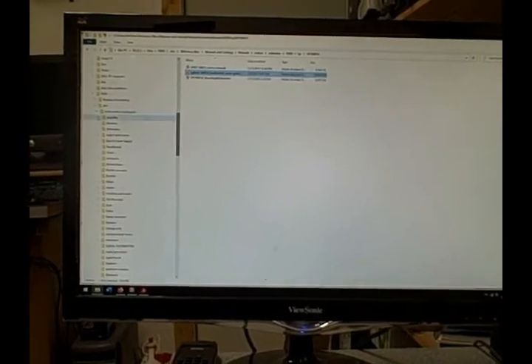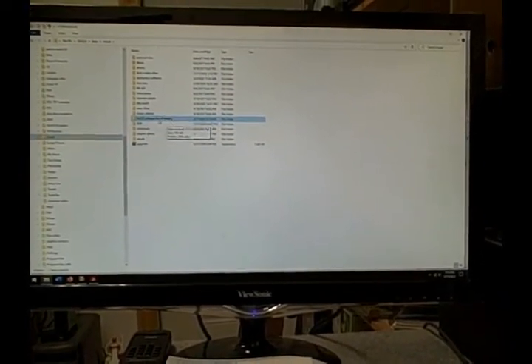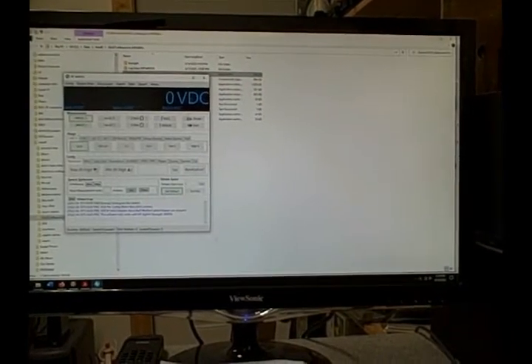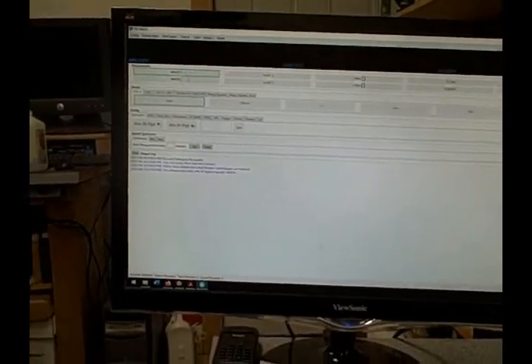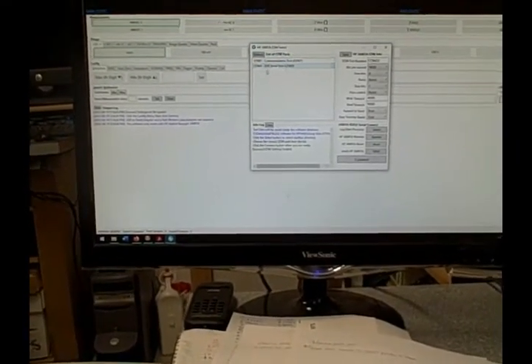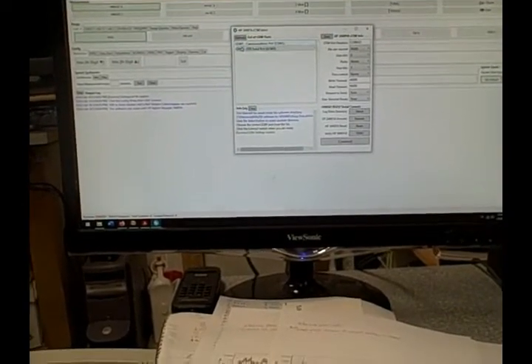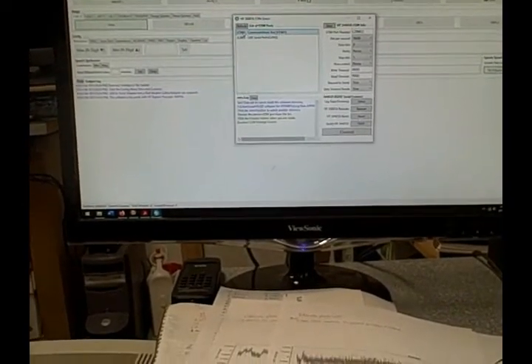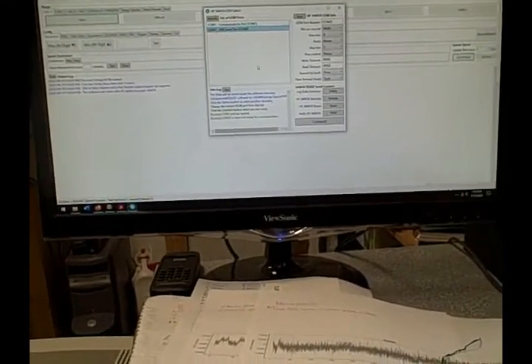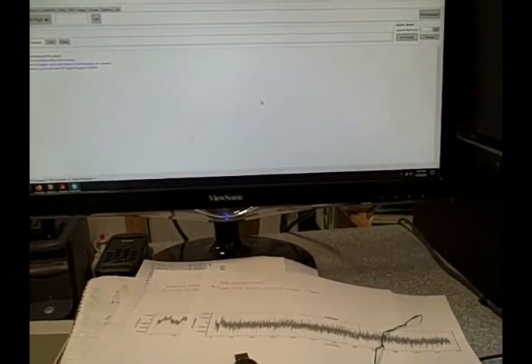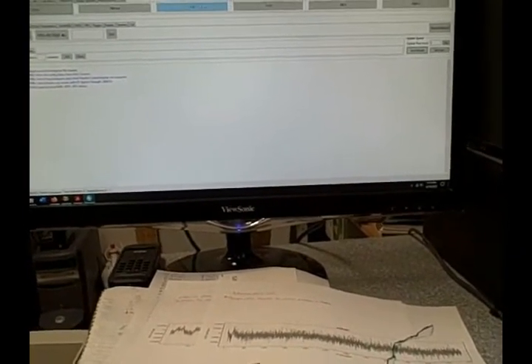I want install. Here we go. RS-232 software. HP 34401A. And there it is. So I'm going to choose to configure and connect. So it brings up a list of RS-232 ports it sees. It sees one on COM1 and one on COM3. Well the COM1 I'm using to communicate to my printer. COM3 is the new one. So I double click on it. It brings COM3 over to this area and I say connect. And I see a reading up here. So I've connected.